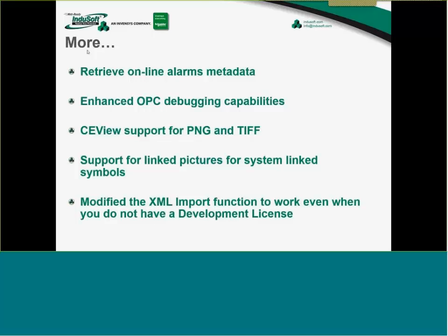So if you're interested in generating screens during the runtime, that's pretty much what you need. And on Service Pack 2, we would require you not only to have a development license, but to have the development license open when you call this function. Now we eliminated that requirement. So you can call the function and your screens will be automatically imported, and you don't need to have a development license. This will work with a runtime only license.